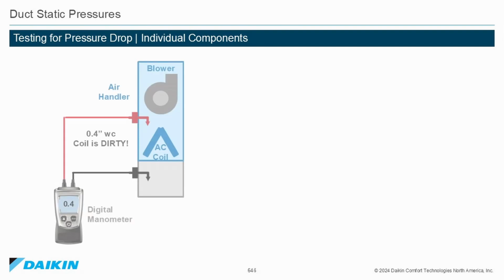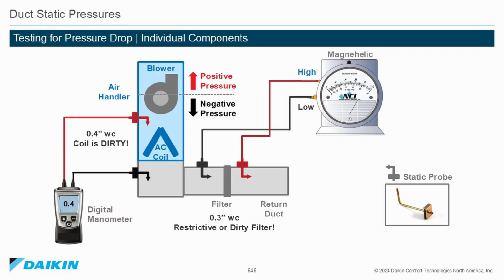Testing static pressure drop on individual components. You can see from this graphic that if your manometer is reading 0.4 inches of water column static pressure between the inlet and the outlet of the coil, the coil is dirty. It also shows if your magnehelic is reading 0.3 inches of water column or more across the air filter, then you have a restrictive or a dirty air filter.